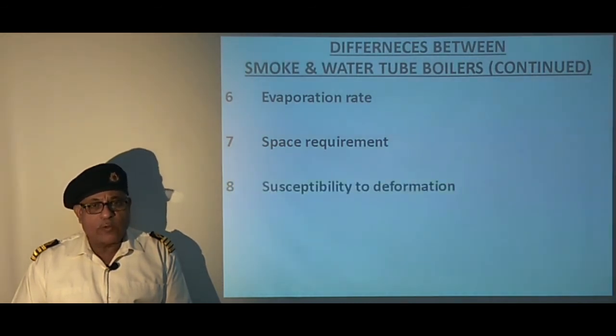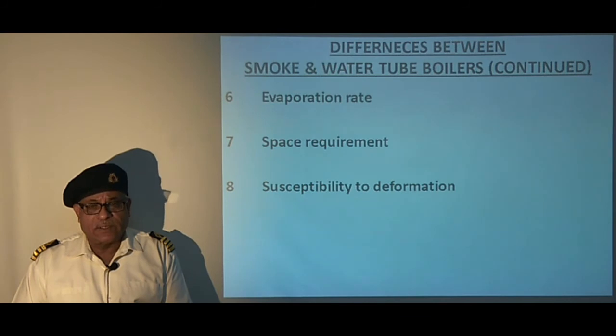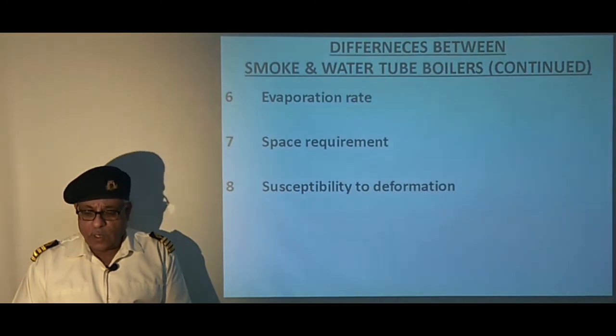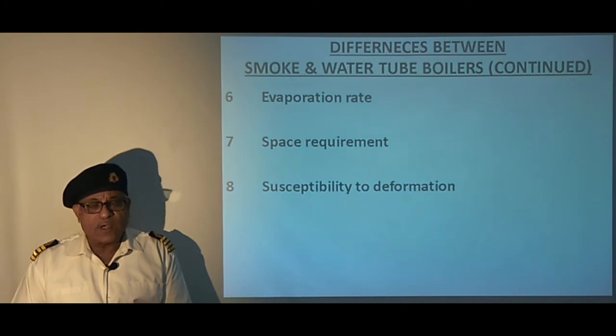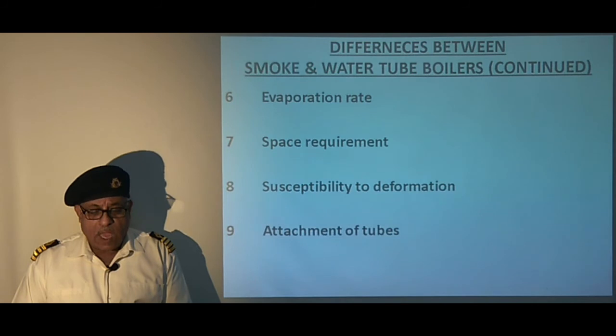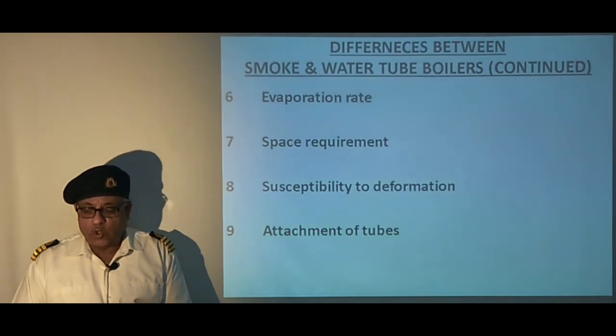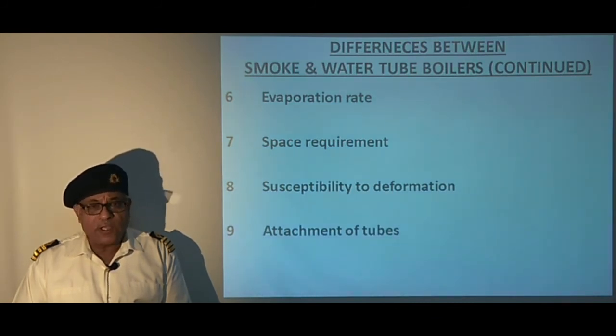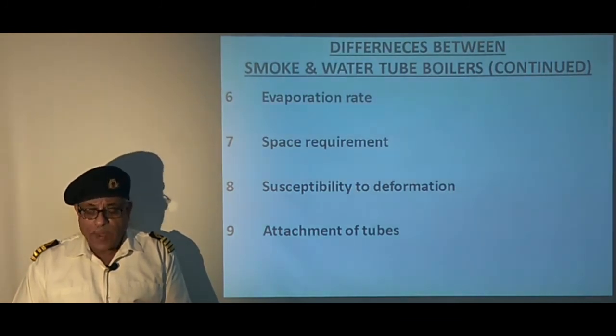As per susceptibility to deformation, the smoke tube boiler furnace is more susceptible to deformation as it is exposed to radiant heat in a compact space, whereas the furnace of the water tube boiler is protected from intense heat and thus provides wider safety margins. Regarding tube attachment, the large diameter tubes of smoke tube boilers are attached by welding, whereas the small diameter and thin tubes used in water tube boilers are easier to bend, expand, and bell-mount.